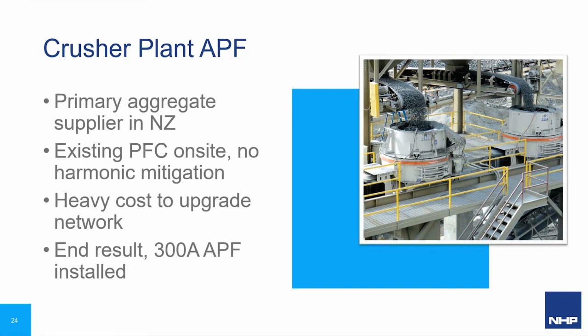So normally, the plant runs with the two supplies separated. That is, the 750 kVA transformer feeds the vital main rock crushing plant, and the generators supply the remainder of the plant. However, during an outage of the 11 kV feeder, which apparently happens fairly often, they have the ability to run the entire plant from generator power.